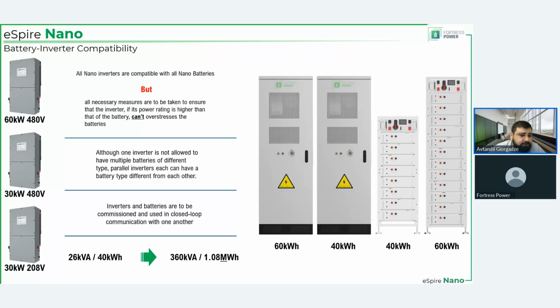So I know that in this industry, everyone says, oh, it's modular, it's scalable. Yes, true. But here's the extreme example for you from Fortress Power, and specifically based on the Nano energy storage system. You can start with as small as 26 kVA power output and 40 kilowatt hour nominal storage system. That will be your one 30K 208 volt inverter and one 40 kilowatt hour battery. And you can go up to 1.08 megawatt hours of storage and 360 kVA of power input and output capability. And even more on the PV side, if you think about it, that will be 600 kilowatts on the PV side.